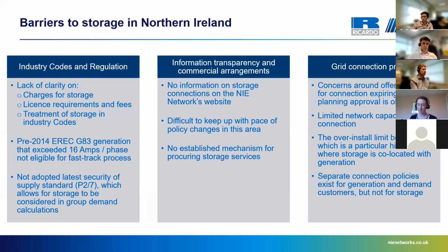And some of the barriers that came out for storage around the grid connection process: some concerns around offer of terms for connection expiring before planning approval is obtained. I think this is a particular issue for storage, where it's a relatively new technology and there can be more challenges in the planning process for things that are less well understood. We've already touched on the limited network capacity for export connections in certain parts of the network. A number of people raised concerns about the over-install limit, which is currently 20%, being a particular hindrance where storage is co-located with generation.